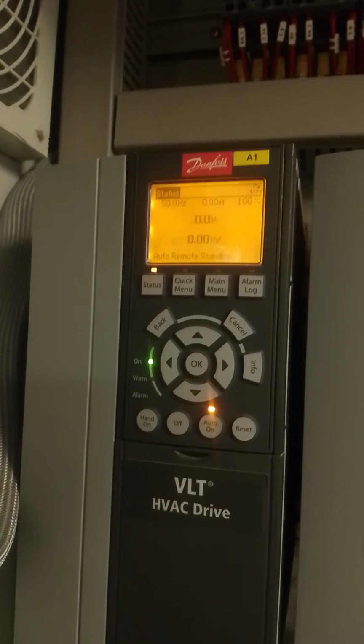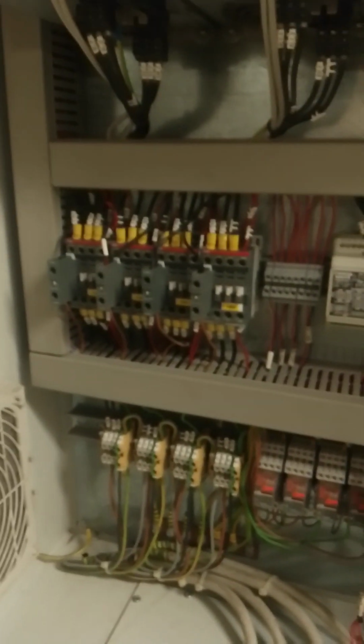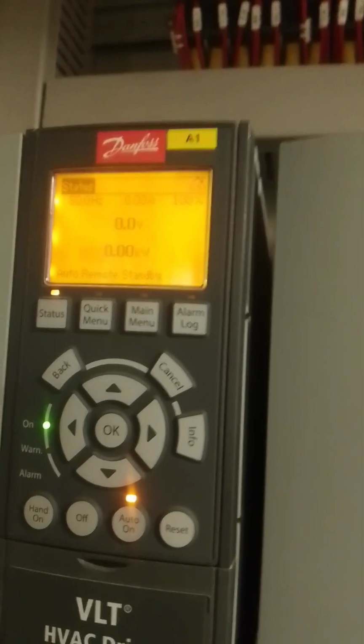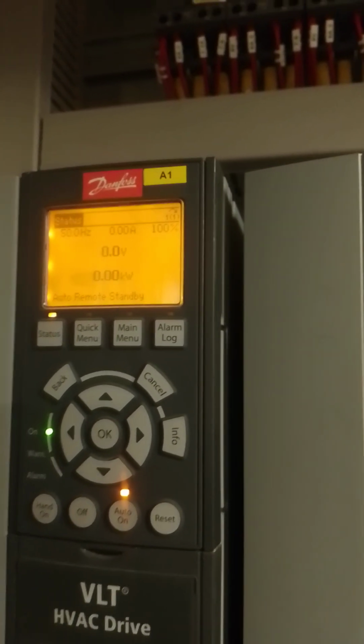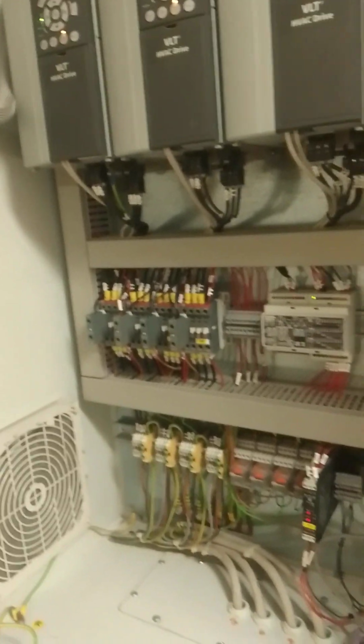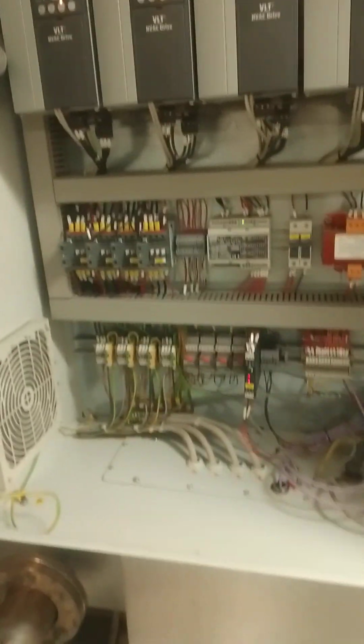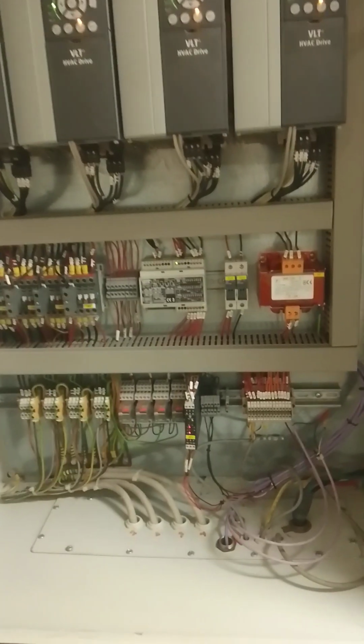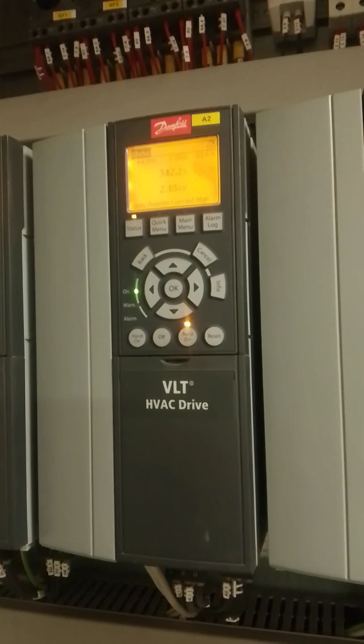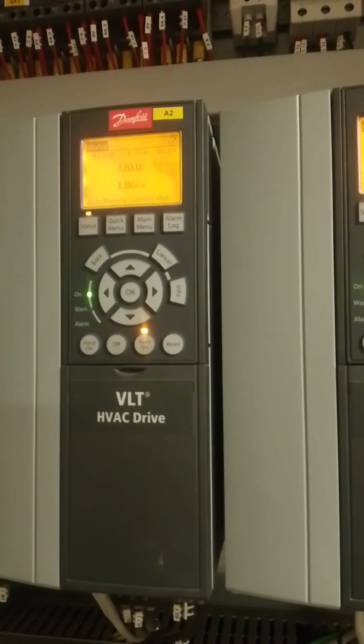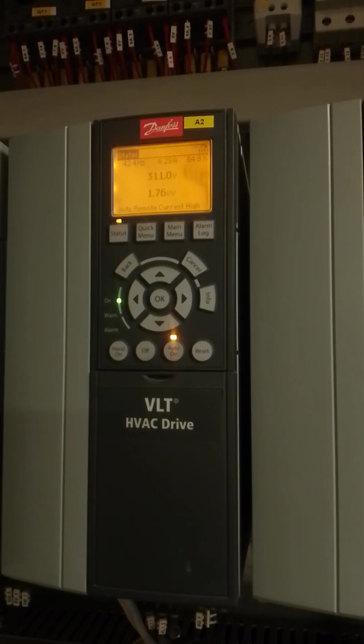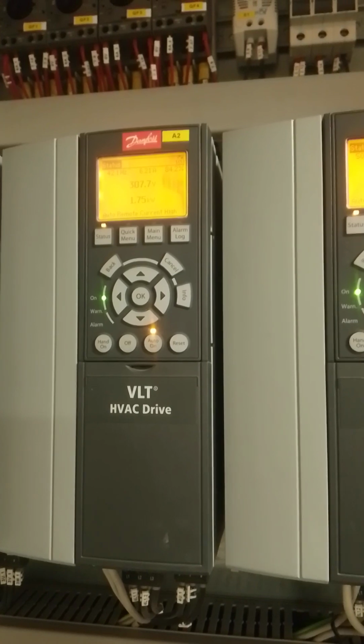You can see now it went off. It's automatic. So as you can see, it's showing auto remote standby. All are at standby. They are also controlled with a pressure switch, which is connected to the motor. You can see now the next one, the second one, is running. Because the setting is to ensure that not only one motor is running; all 4 can run. If there is a lot of pressure, it can run 2 or 3 according to the demand.